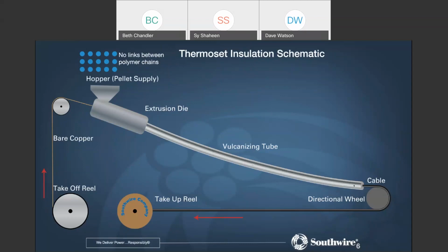But if you'll hit next, it should pop up. There we go. The beauty of this, though, is that the vulcanizing process will now establish this linking between the polymer chains. And what does this do for us? It makes it into a more rugged insulation. Compared to the thermoplastic insulation, the PVC, this material, typically a cross-linked polyethylene, XLPE, is going to have better ability to withstand cuts, gouges, and things of that nature. For the thermoplastic products, what we commonly do for our building wire products is put a nylon jacket over that PVC insulation in order to protect it more. We'll talk a little bit more about that as we progress through the presentation.